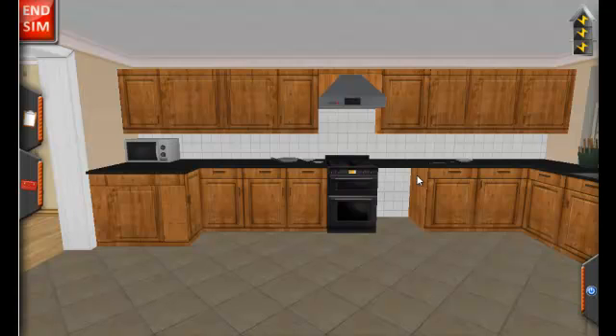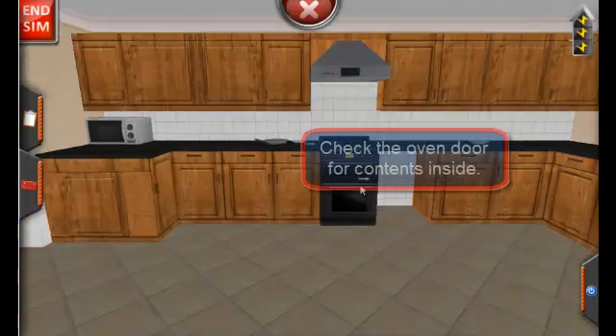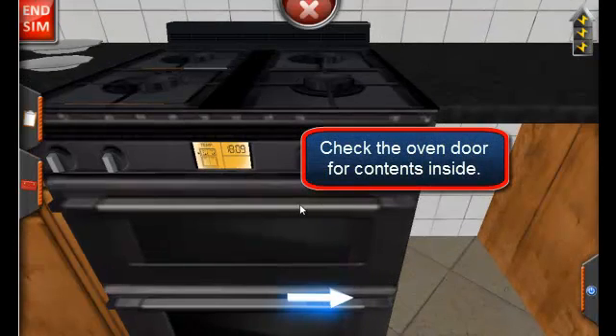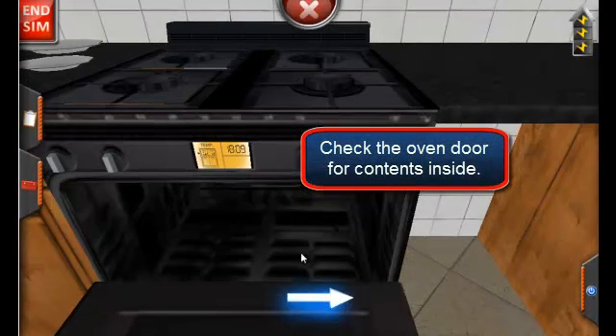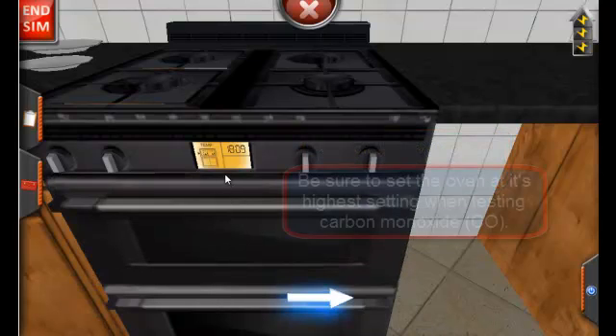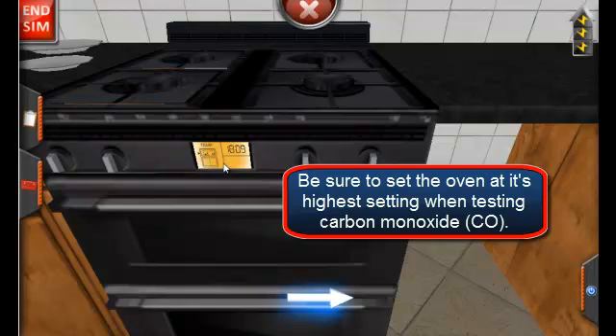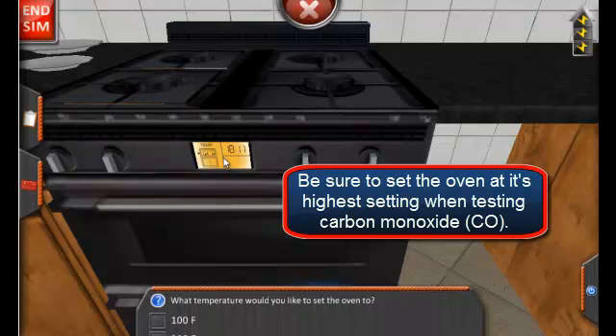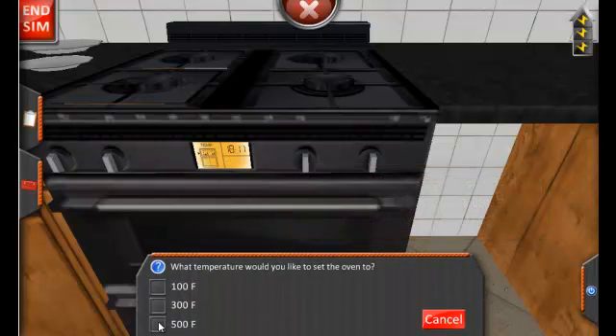There are three functional pieces to the oven. The first is the oven door. Be sure to check for contents in the oven prior to conducting any testing. The second is the oven itself. When testing flue gases for the oven, be sure to set it to its highest setting — in this case, 500 degrees.